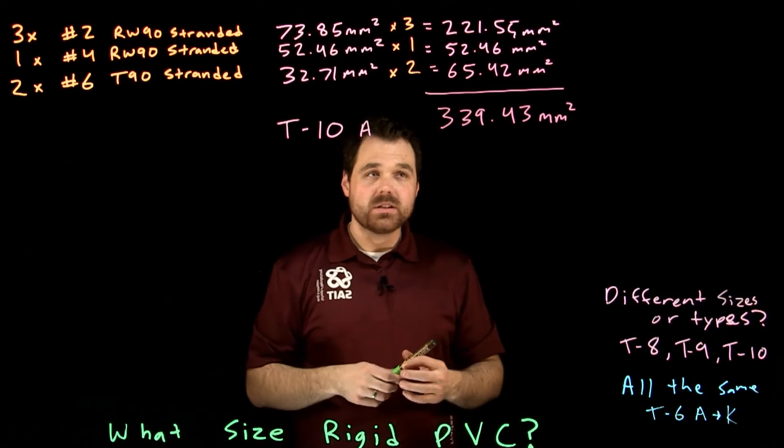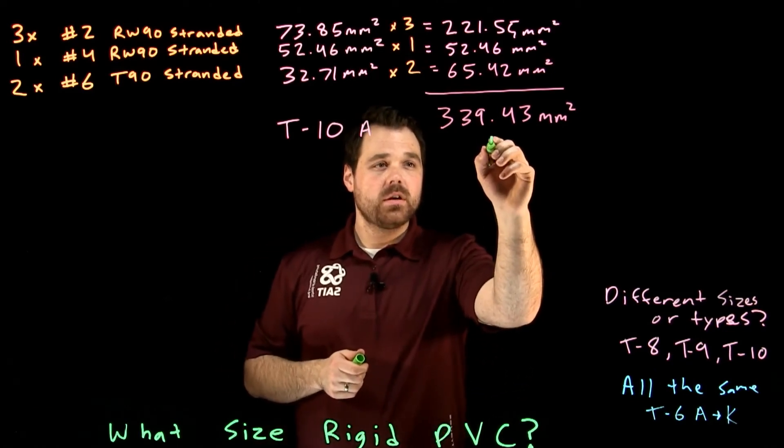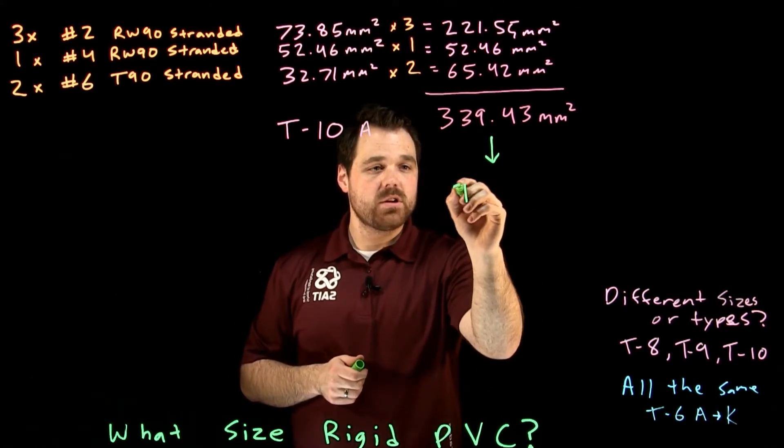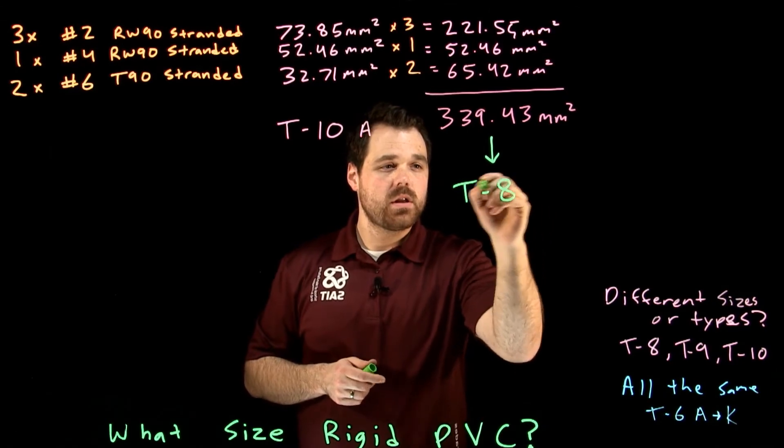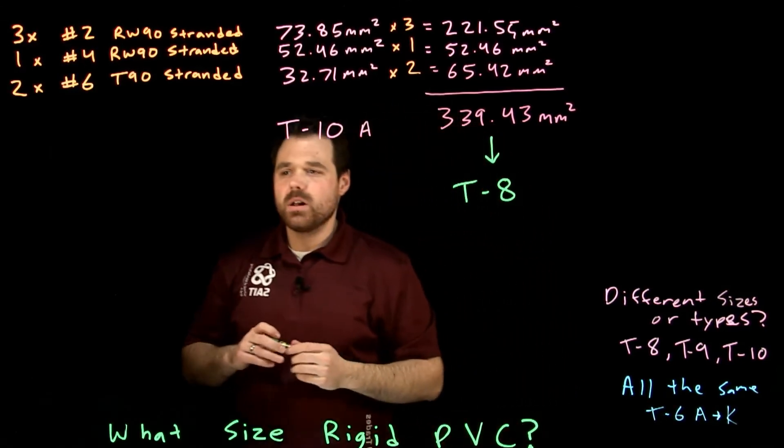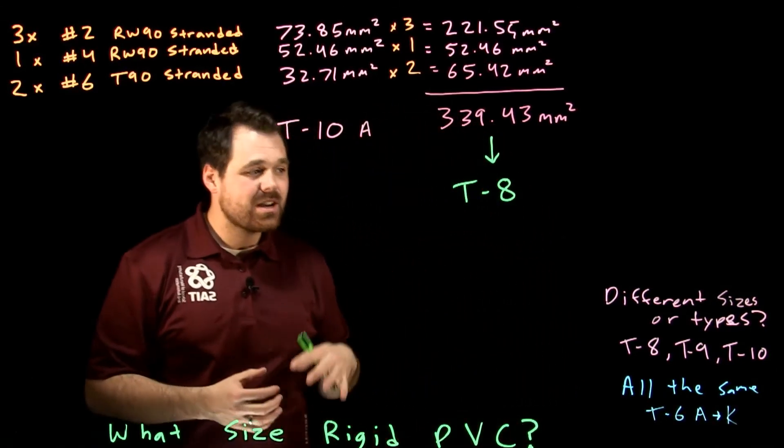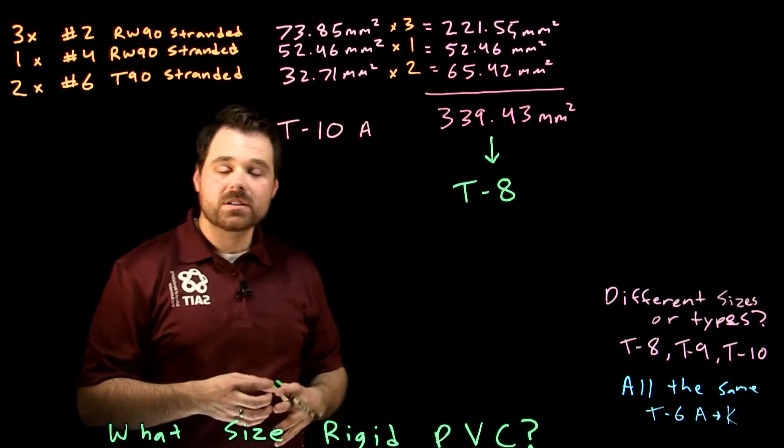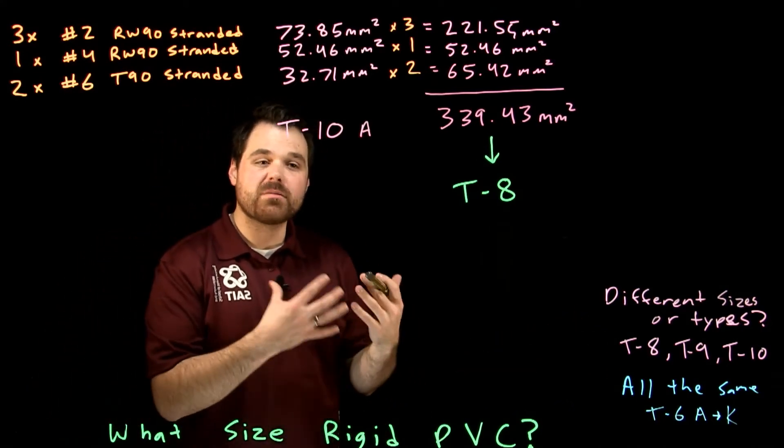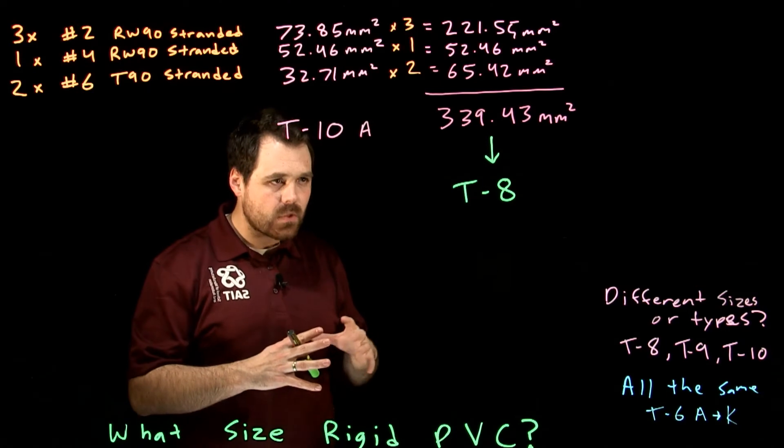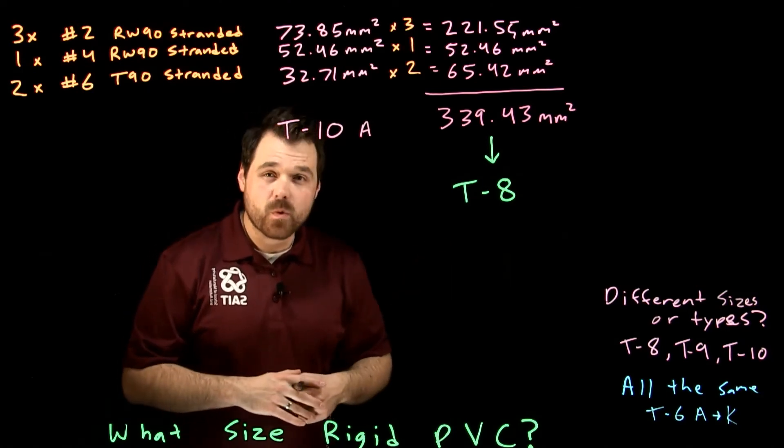Now what we have to do next is we have to take this number and we're going to go to table eight. Now what table eight tells us, table eight is actually telling us how much space you are allowed to take up in that conduit. So it's usually around forty percent.